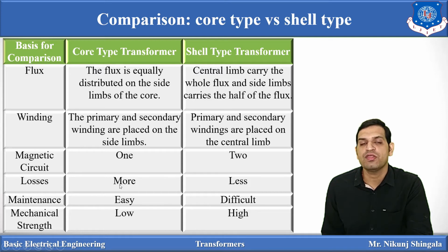The losses are more in core type transformer. In shell type transformer, losses are less. Maintenance is easy because both windings are on different limbs. Here windings are on the central limb, so maintenance is difficult. Then mechanical strength is low because a considerable part of the winding is exposed to the air. Here a considerable part of the winding is surrounded by the core, so it has high mechanical strength as compared to the core type transformer. So these are the parameters on which core type and shell type transformers are differentiated.